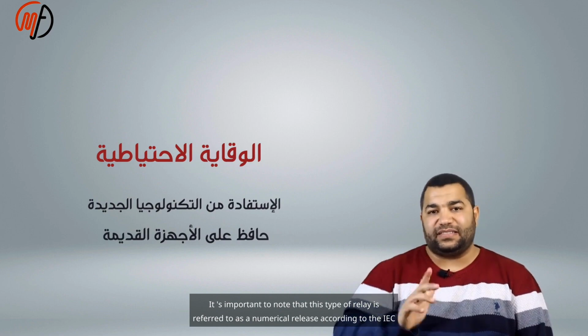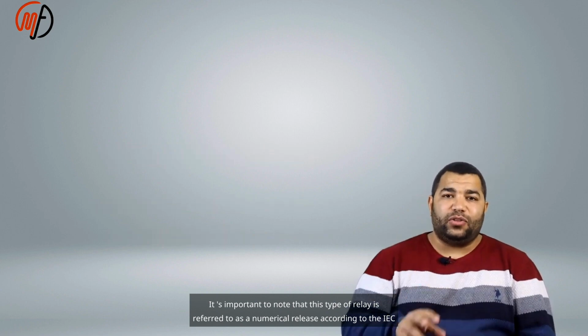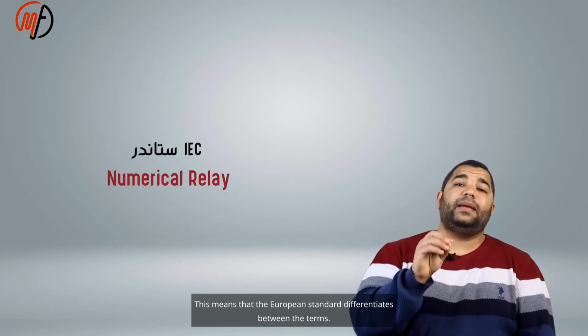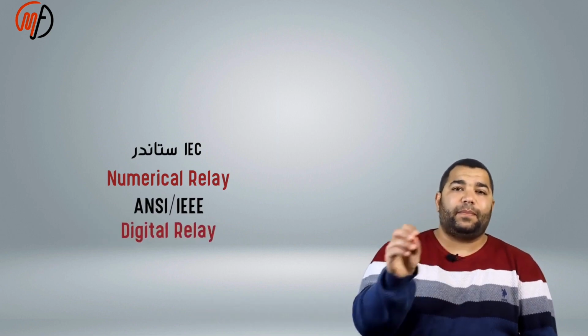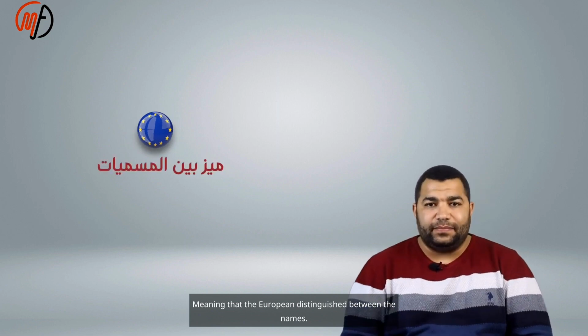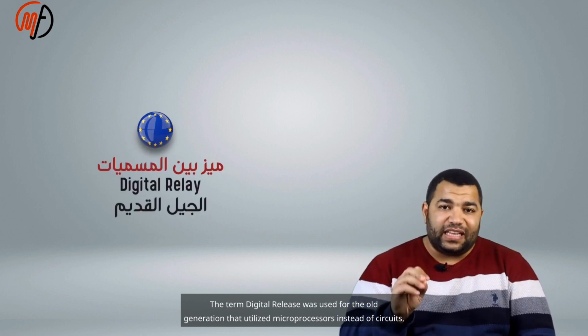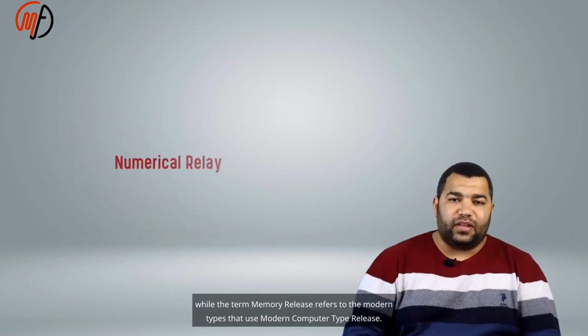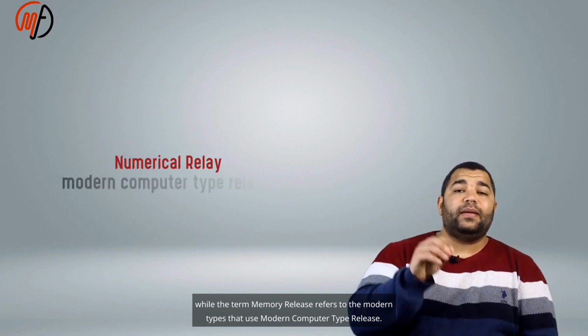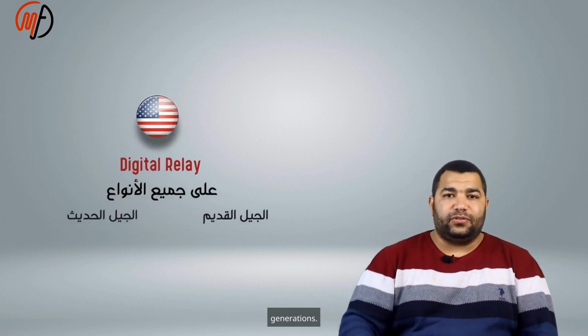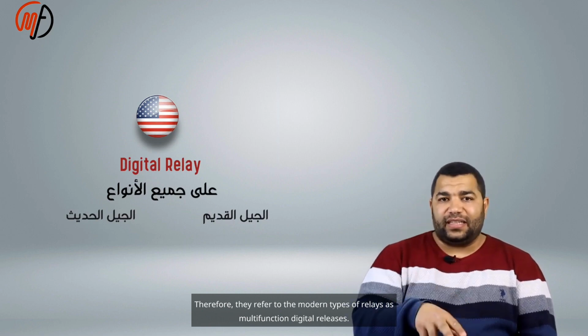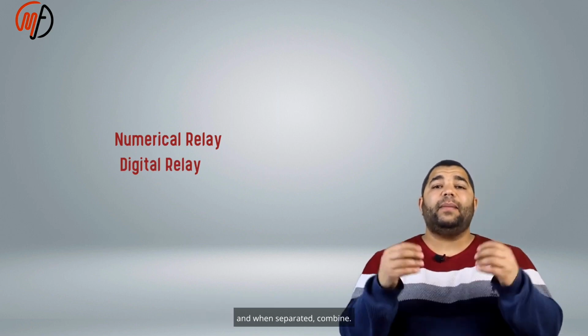It's important to note that this type of relay is referred to as a numerical relay according to the IEC standard, while the same type of relay is called a digital relay according to the American IEEE standard. This means that the European standard differentiates between the terms. The term digital relay was used for the old generation that utilized microprocessors instead of circuits, while the term numerical relay refers to the modern types that use modern computer type release. The American standard, on the other hand, used the term digital relay for all types, both old and modern generations. Therefore, they refer to the modern types of relays as multifunction digital relays. This means that the terms numerical relay and digital relay are two words that, when combined, separate, and when separated, combine.